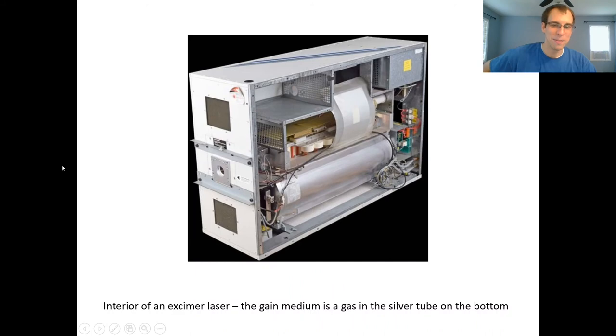This is what the inside of an excimer laser looks like. I don't remember which model this one is in particular, but the actual lasing medium is this part down here, this big silver tube on the bottom. That's where the actual gases go to generate the excimer laser. And you can see some of the capacitors here. Most of the rest of this is just electronics to generate that electric discharge at the right repetition rate and frequency.